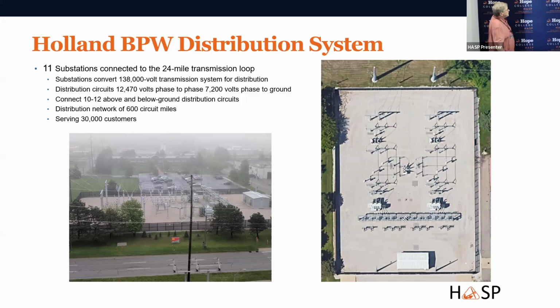There are 11 substations connected to that loop. They convert the 138,000 volt transmission down to 12,000 volts, and connect between 10 and 12 above or below ground distribution circuits that go out to homes and factories. There's a network of about 600 circuit miles, and we serve about 30,000 customers.